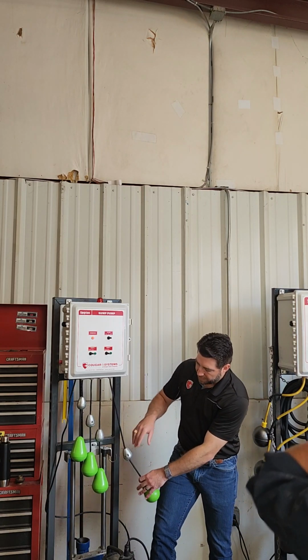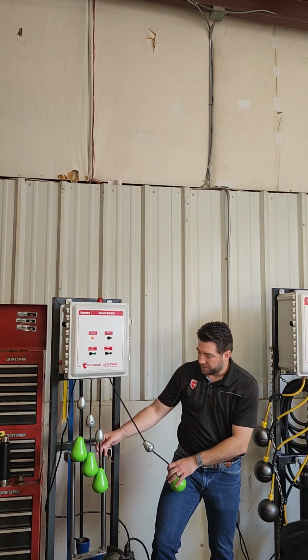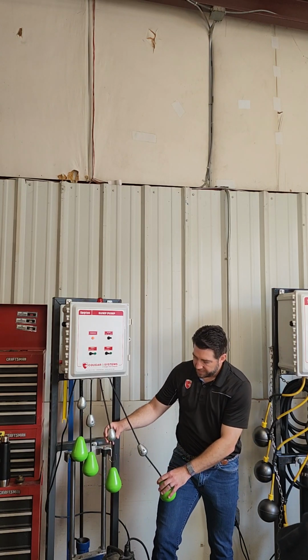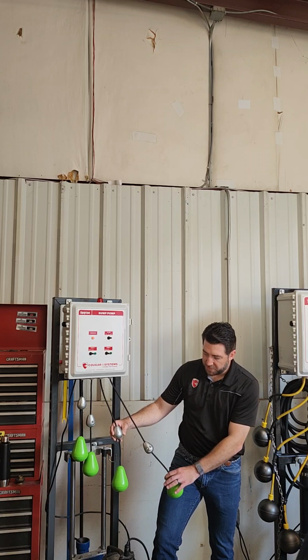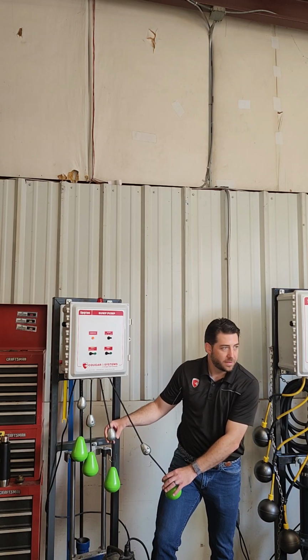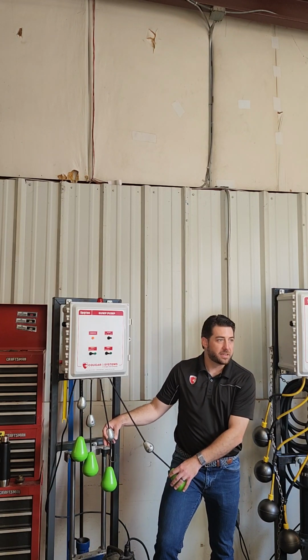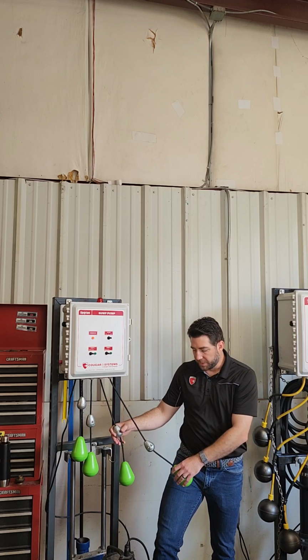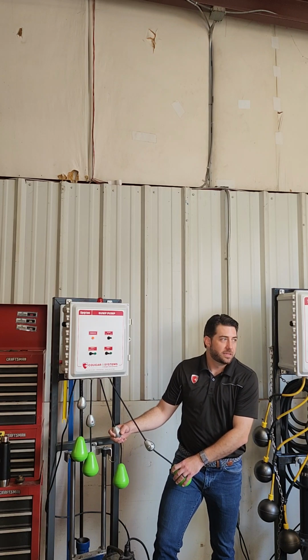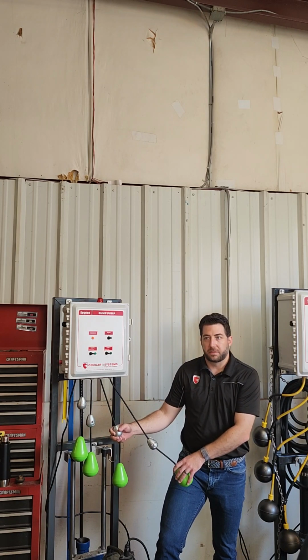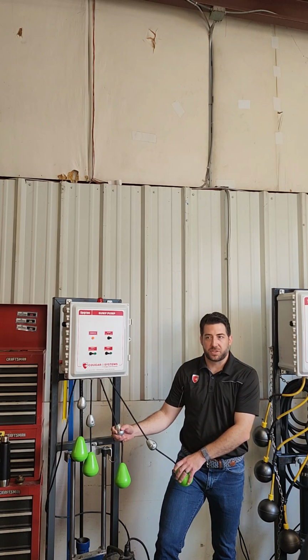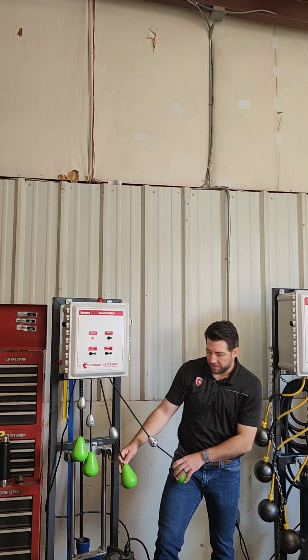Because you're separating out when the pump turns on and off into 2 separate floats. So the pump down range is going to be the difference between these 2 floats. Okay? So the longer you can get, the better. The pumps typically don't want more than 20 starts an hour. So the most pump down you can get out of the pit you want, especially if you're using the grinder. And you no longer pump down with the grinder.